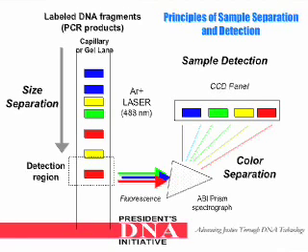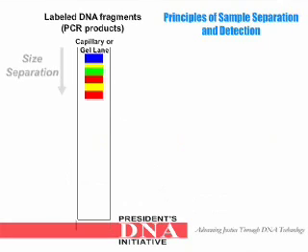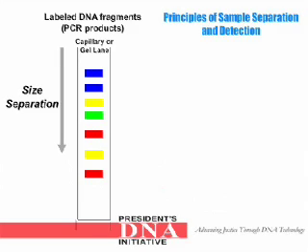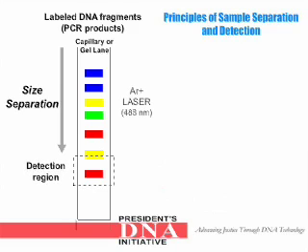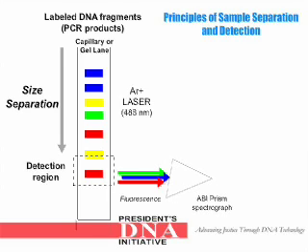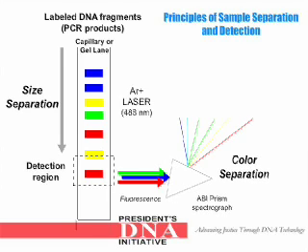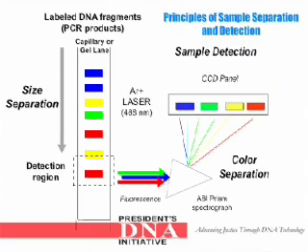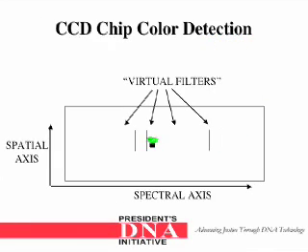This animation shows the detection of separated samples. First, there is size-based separation of the dye-labeled PCR products. Then, excitation of the dyes by the argon-ion laser. This is followed by emission of the fluorescence, which is detected on a CCD camera that sorts the dyes based on their wavelength. The CCD camera, which stands for charge-coupled device, has virtual filters which separate the different emissions of fluorescence from the dyes based on their wavelengths.